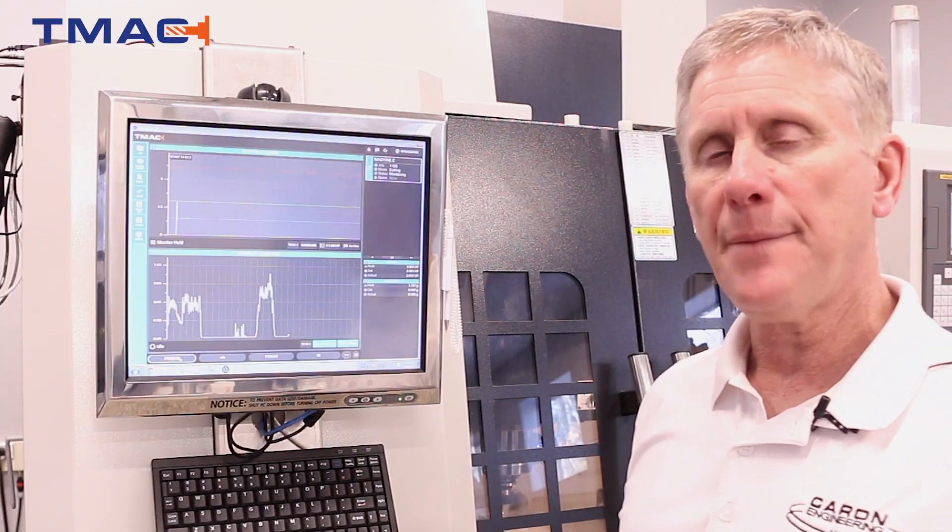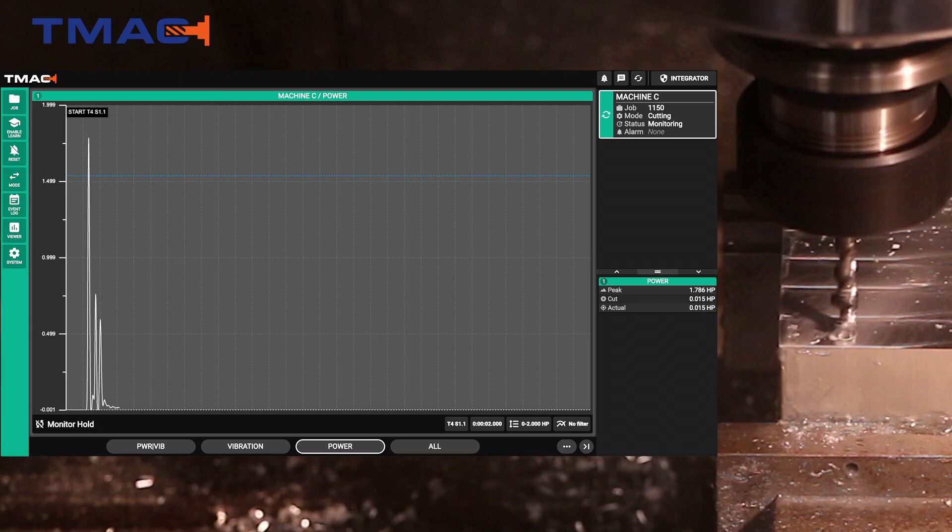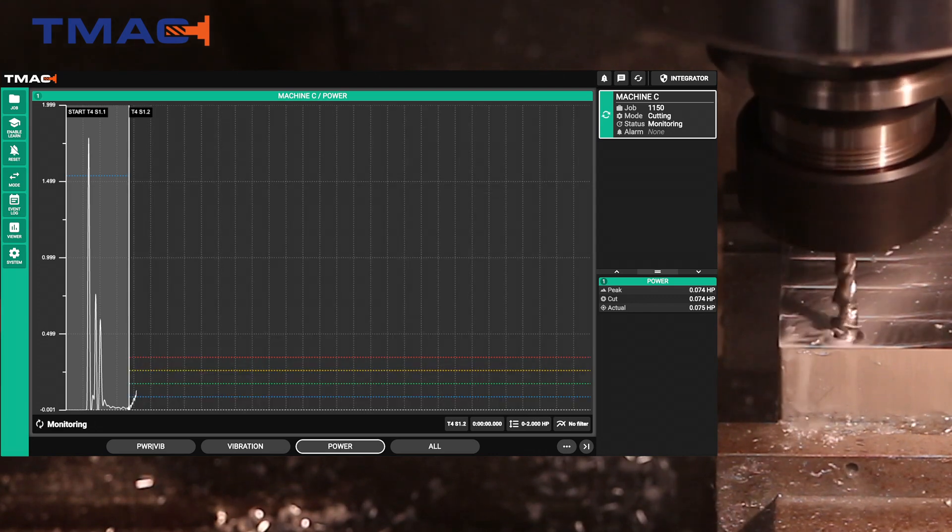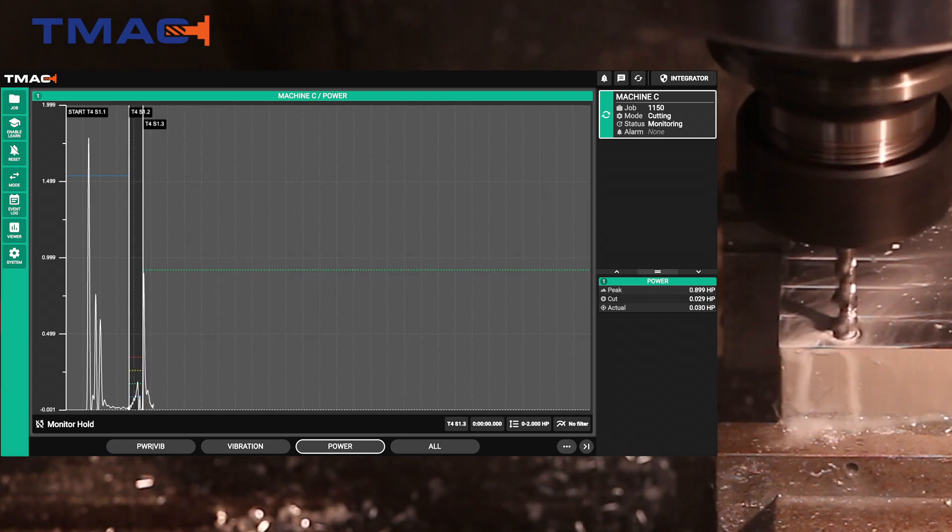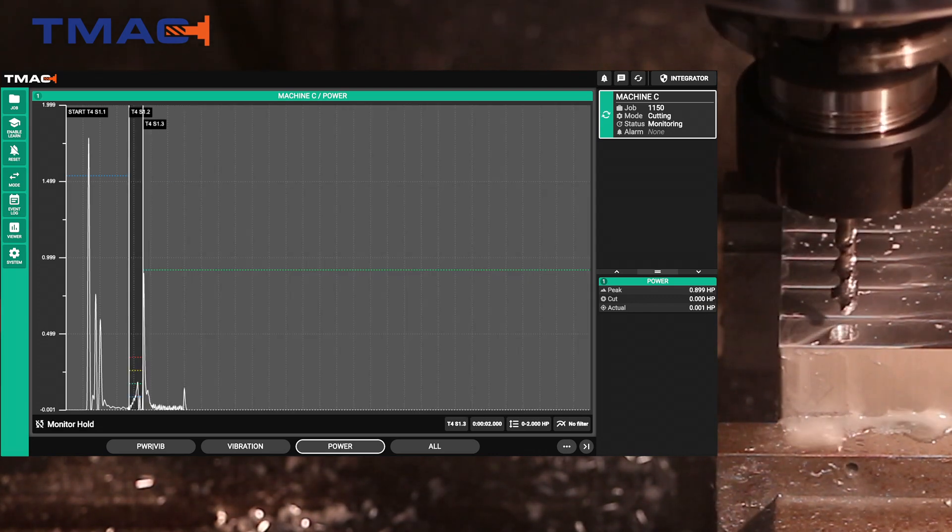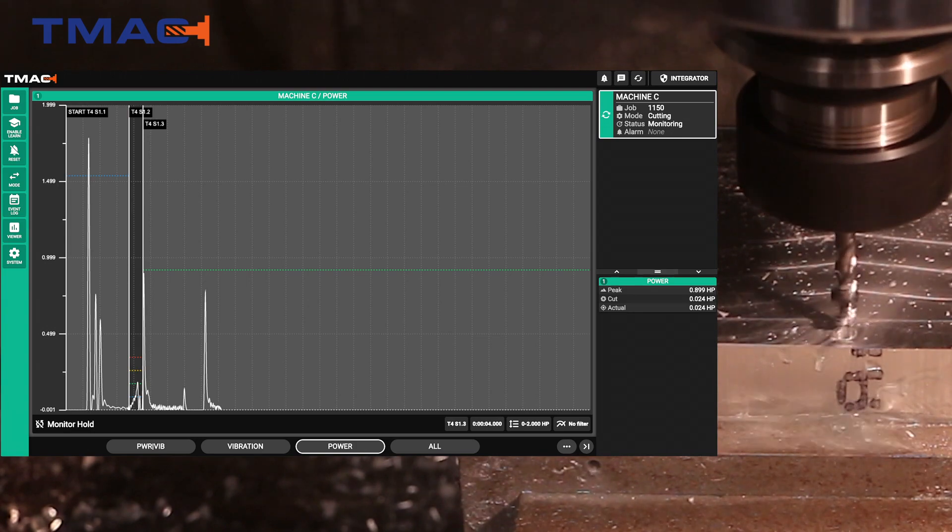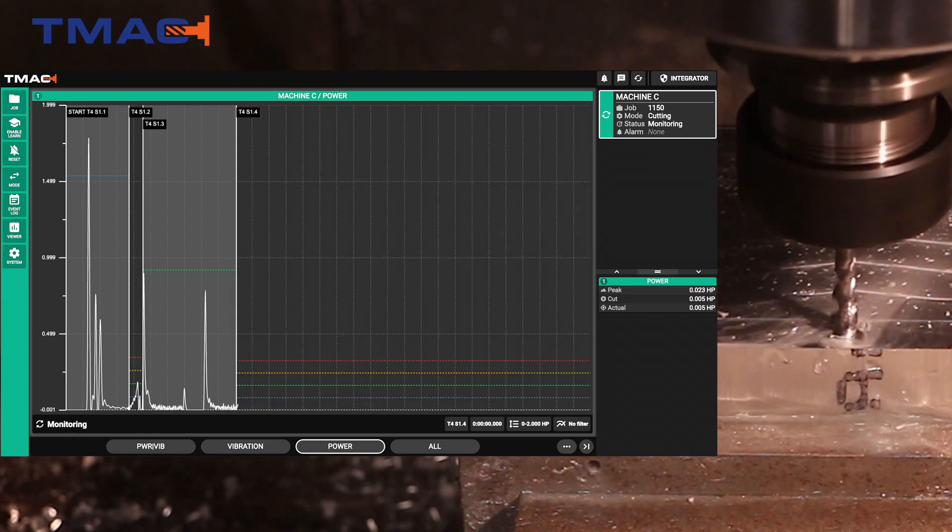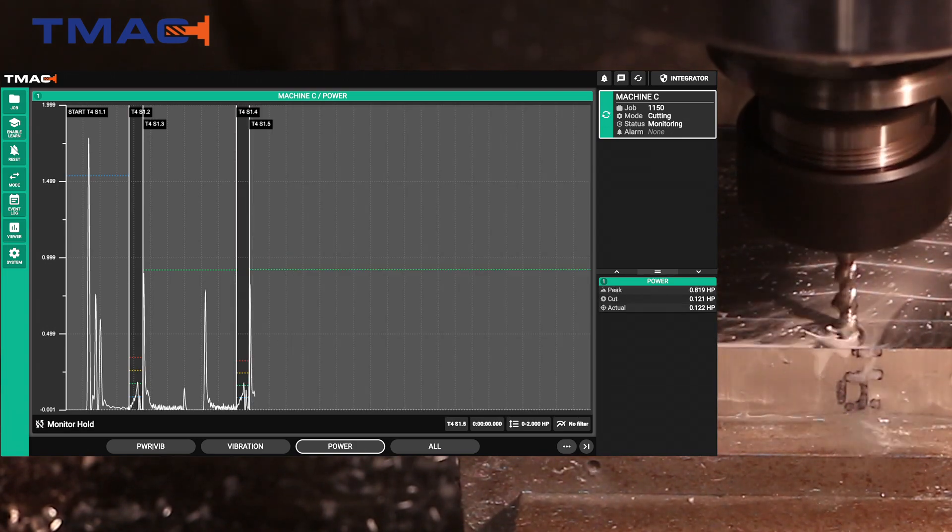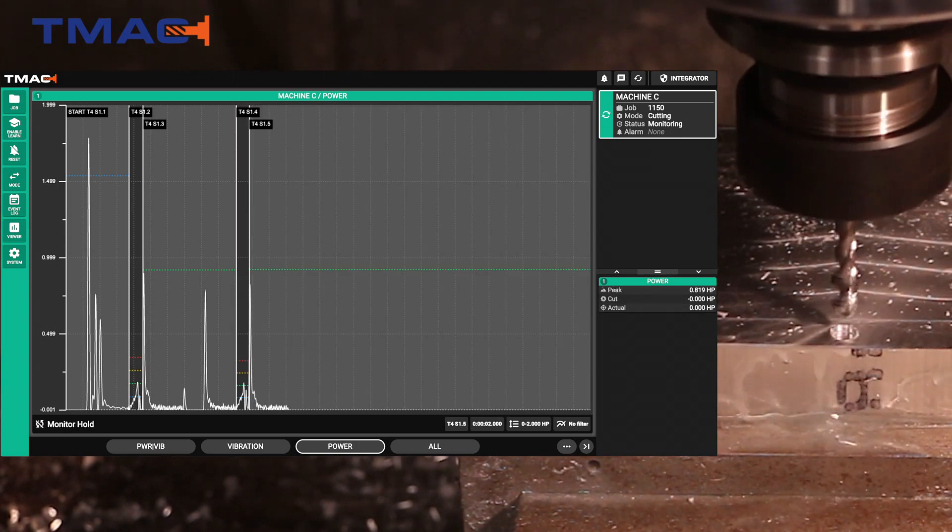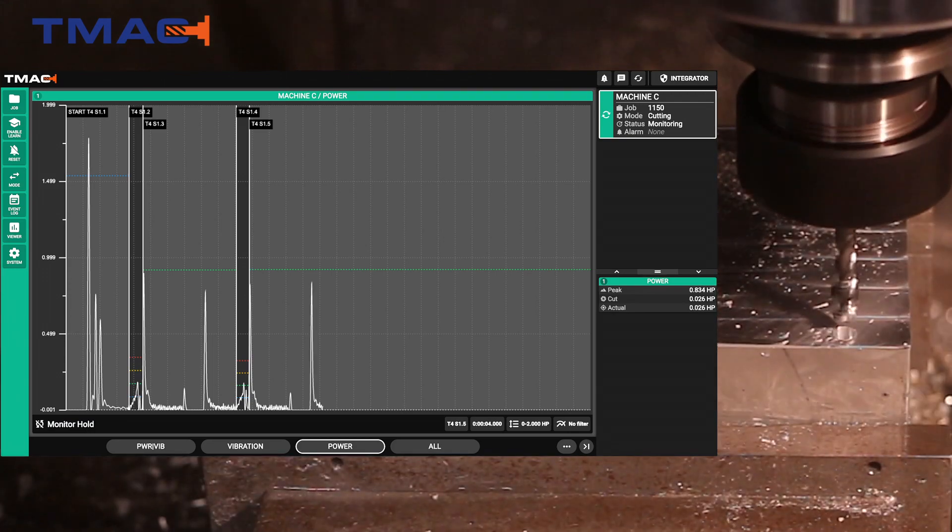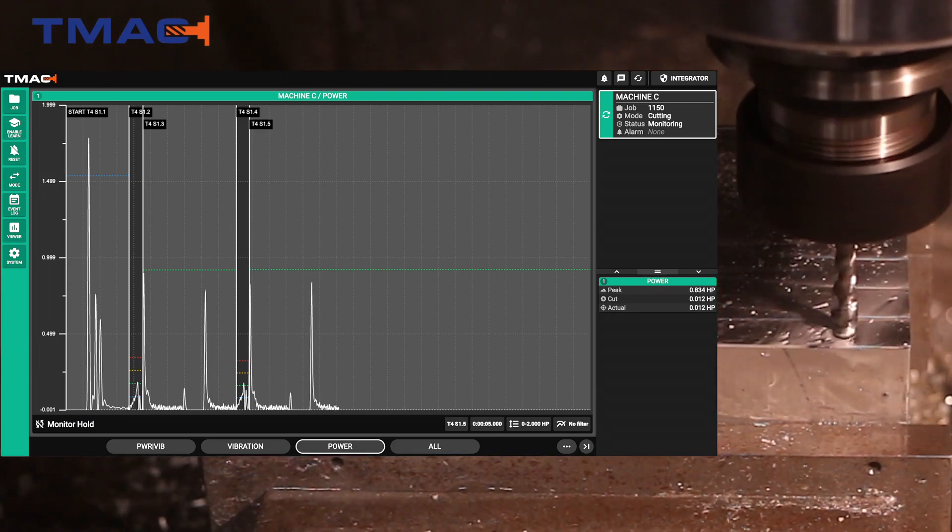Now we're going to show tapping where we're using a technique called time slicing. Here we're looking at the gray area is all the reversals of the spindle and are ignored. The black area is when we're actually monitoring the cutting of the tap. It's only in its forward motion that we monitor.